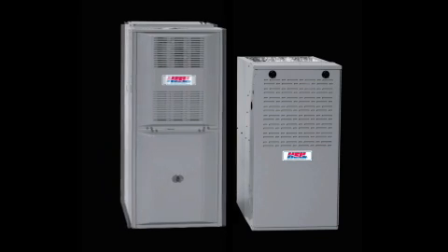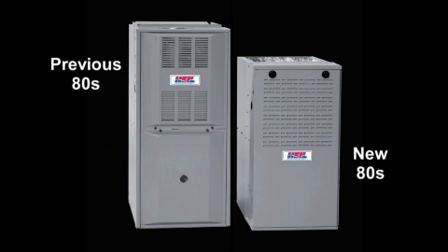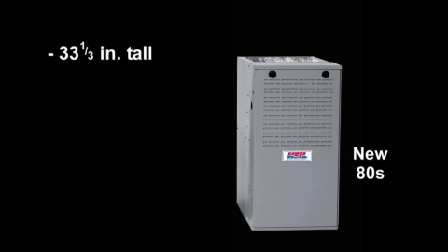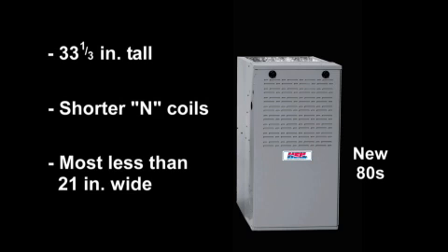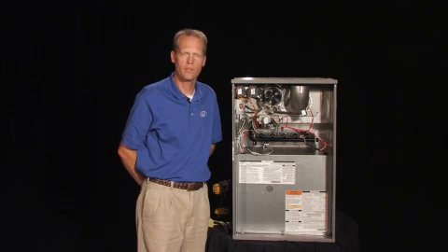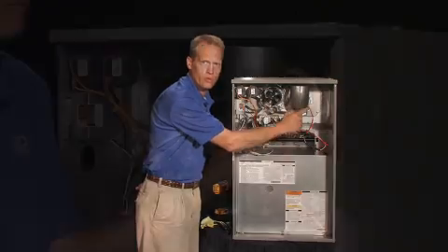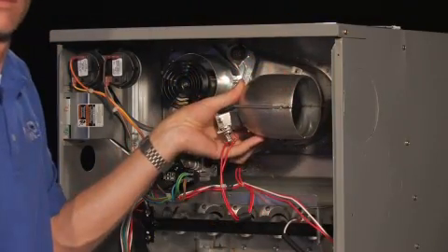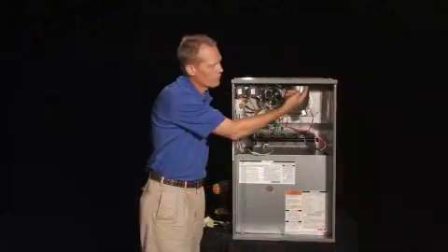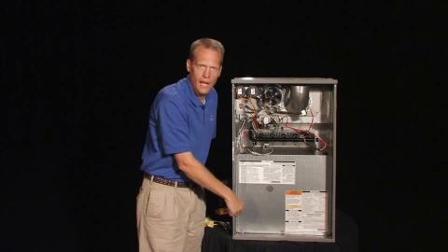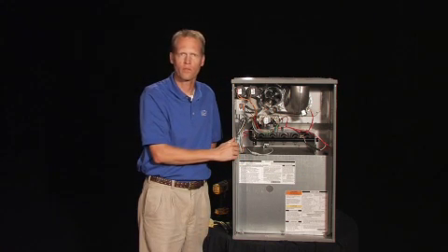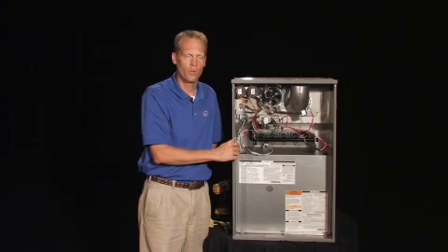But some of the most popular features are the ones that make these furnaces so much easier to install and service. They are just 33 1/3 inches tall, plus they can also be matched with new N coils that are several inches shorter than existing A coils, so the effective height of the furnaces can be lower. Plus, most models are less than 21 inches wide for easier installation in tight spaces. All models are capable of 4-way multi-position installation. Remove just 3 screws, and the vent pipe can be twisted to 3 different positions. There are 5 knockouts in the cabinet, and the vent pipe can be positioned into 13 different configurations. That should give you an option for any installation.